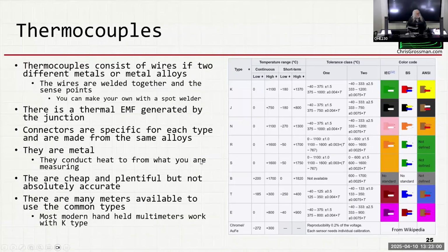Now let's talk about temperature measurement. That's very important. One of the easiest, most common ways to do temperature measurements is thermocouples. Thermocouples are just two different wires of different materials, welded together at the temperature point. You could spend $10 or $15 per thermocouple when you buy them, or you could get a little spot welder and just do it yourself. You cut the thermocouple wire, plunk it to the spot welder, and you're done. It works just as good.